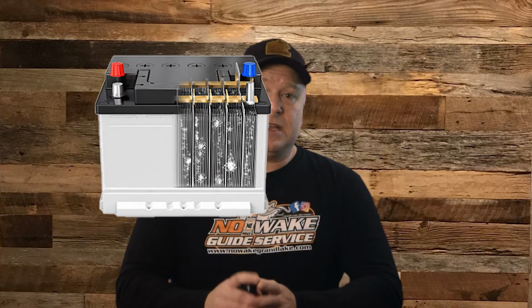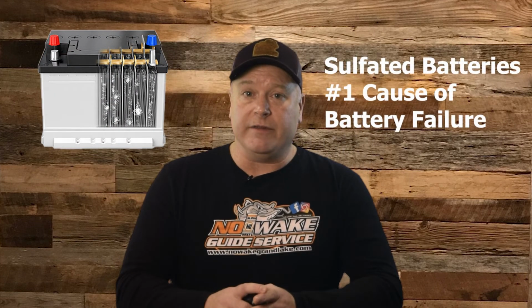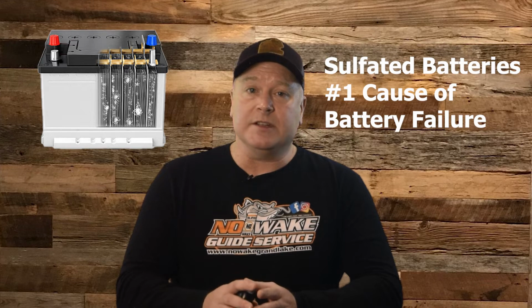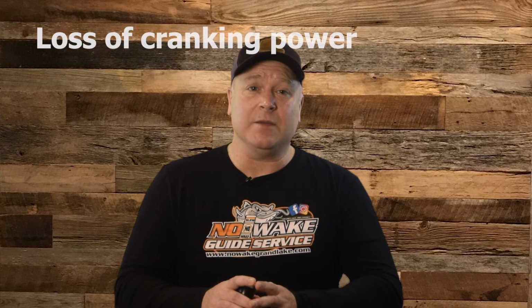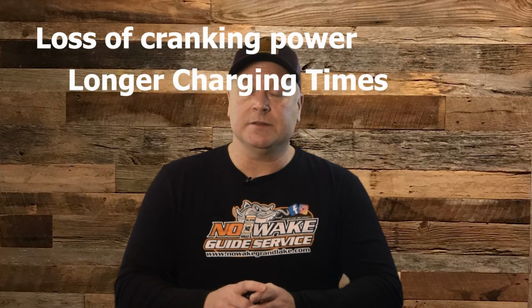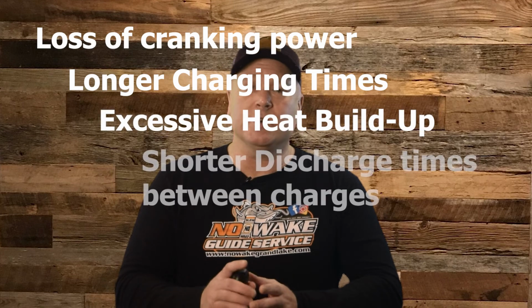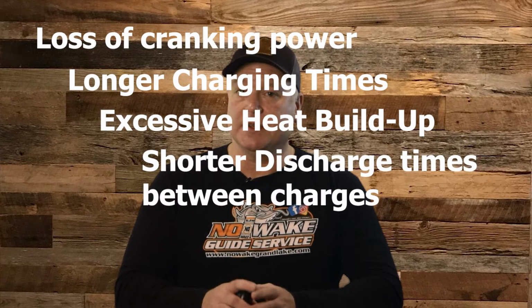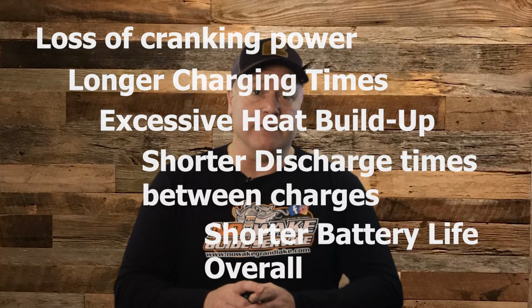If not charged regularly, lead acid and absorbed glass mat or AGM batteries can experience a condition called sulfation. This buildup of lead sulfate crystals is the #1 cause for early battery failure. Sulfated batteries can experience loss of cranking power, longer charging times, excessive heat buildup, shorter discharge times between charges, and dramatically shorter battery life overall.